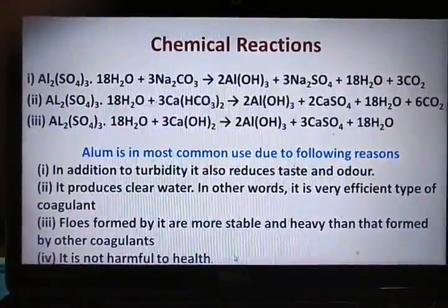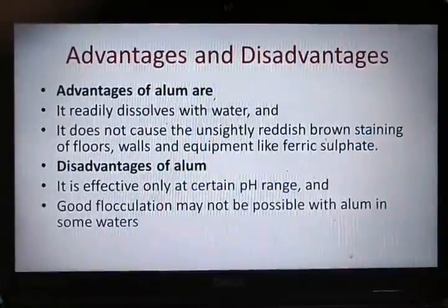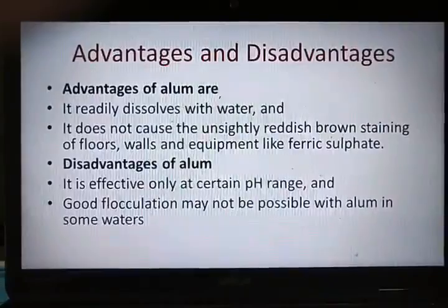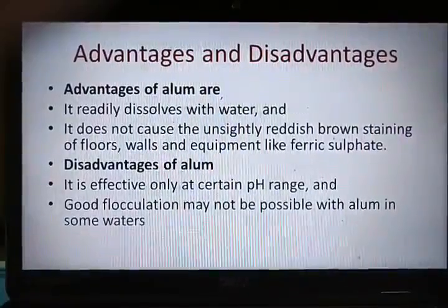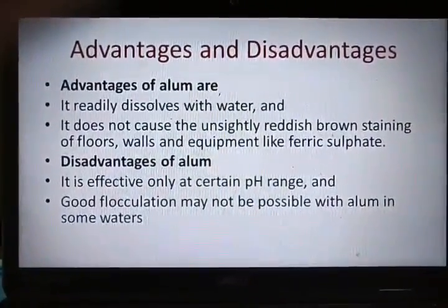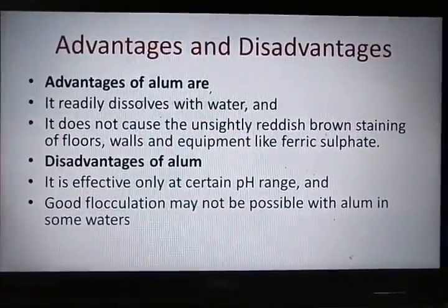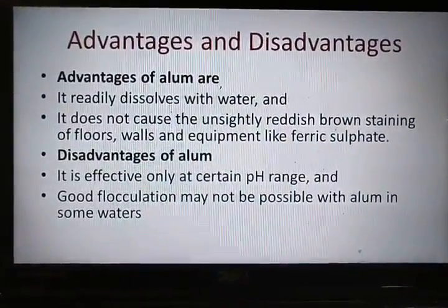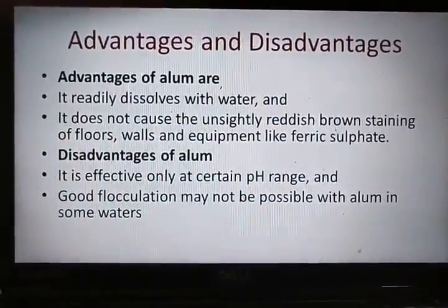Due to these reasons, alum is extensively used in the treatment of water, and these are some of the advantages and disadvantages of alum. Alum readily dissolves in water, so it becomes easy to mix the alum with the water with minimum effort, and also it does not cause any unsightly reddish brown staining of floors, walls and equipment like ferric sulfate.